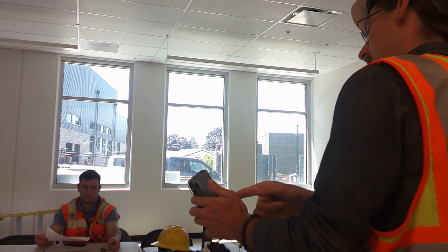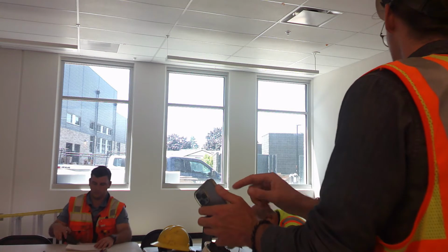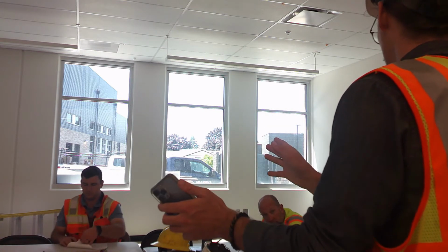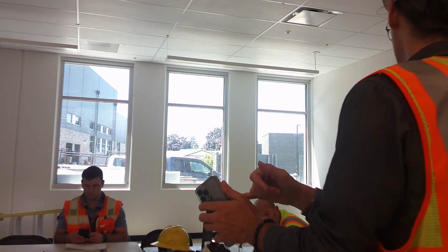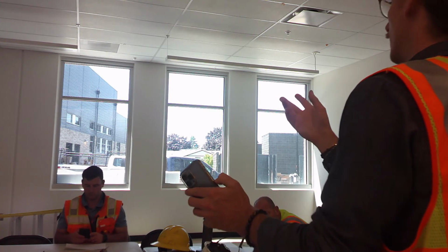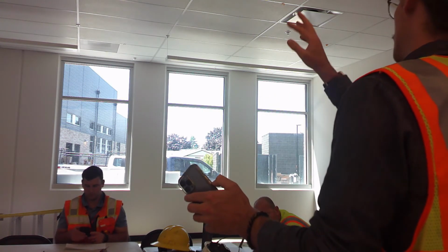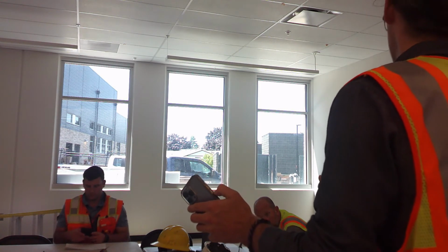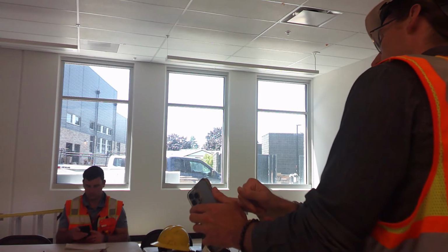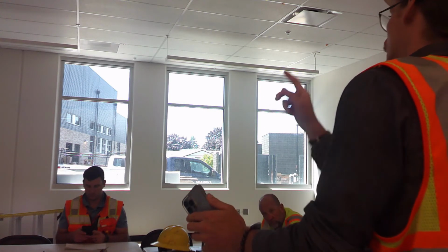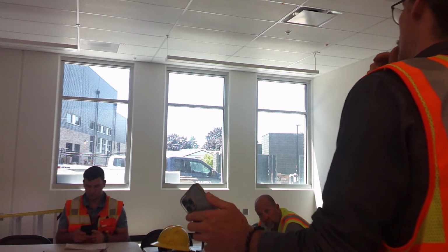So if your design and task are at the same number, then they cancel out of the equation. The ratio is 1. So it's just 1 times whatever your sensor value is, then I guess divided by how much the photocell is picking up. So if I go back here, I can see that the daylight level there is 220, so that photocell is picking up quite a bit of light in there.